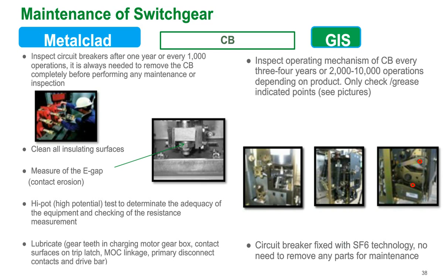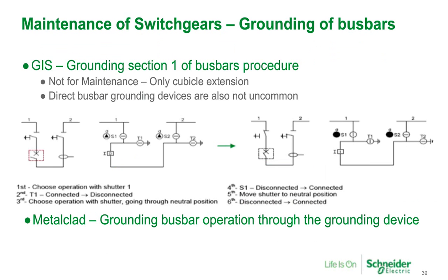The last part is talking about grounding, because in a metal clad, typically you're using a hook stick and some grounding leads, which is kind of the old way of grounding, or you use a rackable ground and test unit, which requires that you remove the circuit breaker and rack in a ground and test device, which may have some very special interlocking on it. With GIS, all of that is integrated into the switchgear, so there's no external devices needed to ground the bus bar or the circuit breaker. All of this is also interlocked so that there's no way of improperly grounding potentially live bus bars or potentially grounding a feeder section or feeder breaker when there is voltage present.